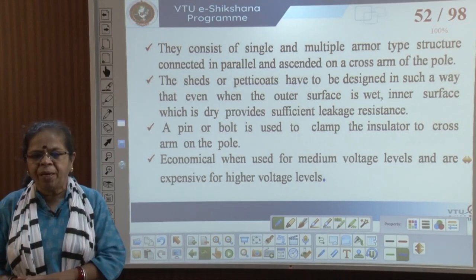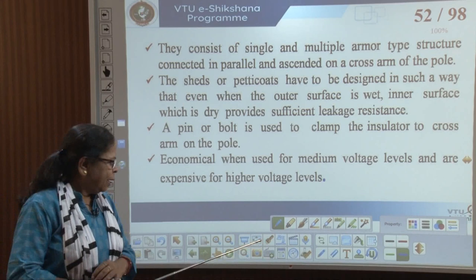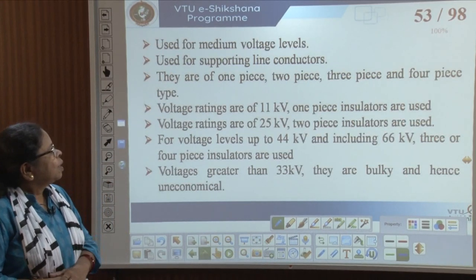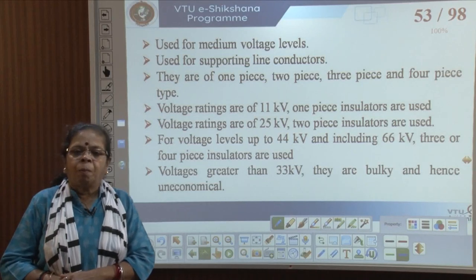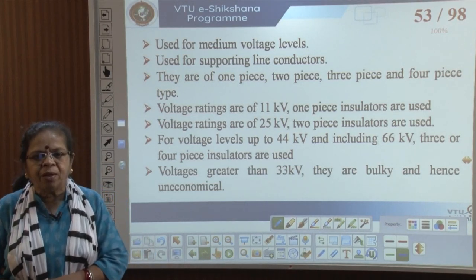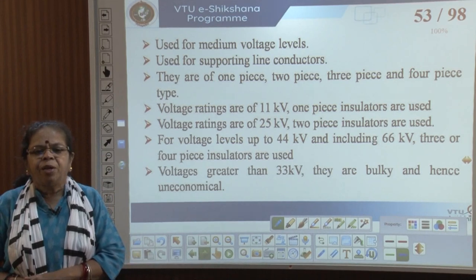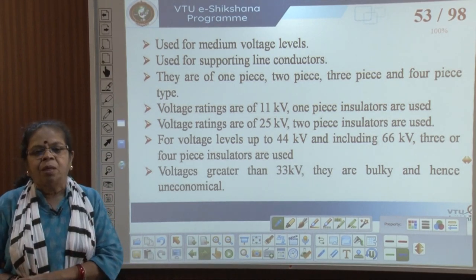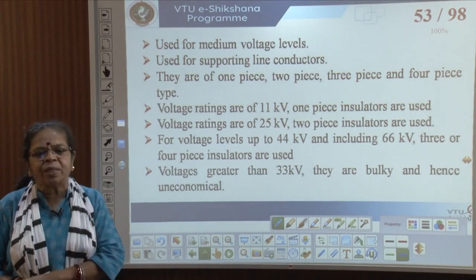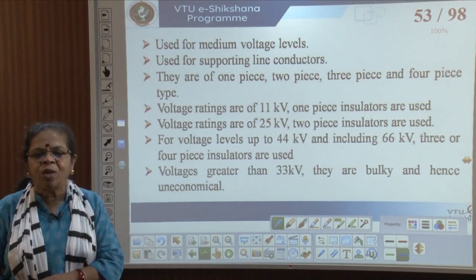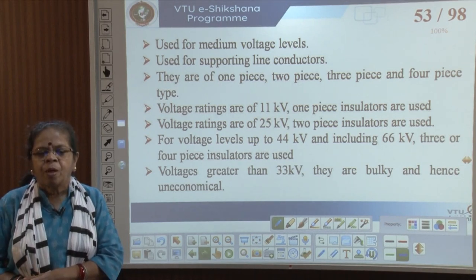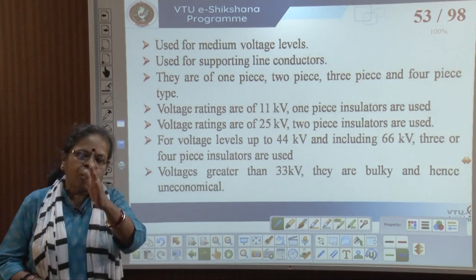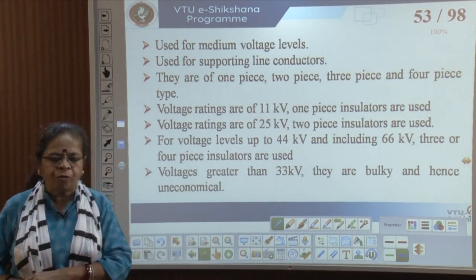Pin insulators are used for supporting line conductors. Voltage ratings of up to 11 kV use one insulator, up to 25 kV use two insulators, and up to 44 kV use three or four pieces. For more than 33 kV they become bulky and we go for the suspension type of insulators.